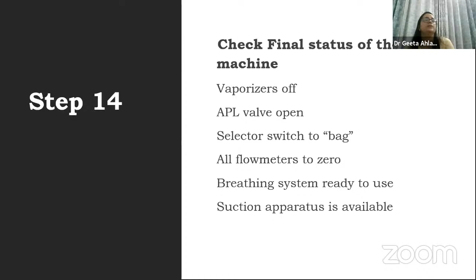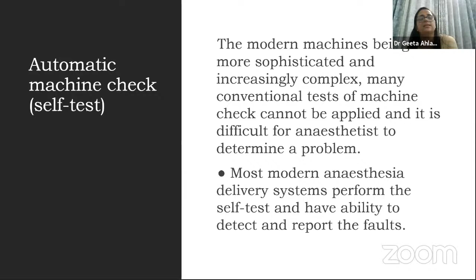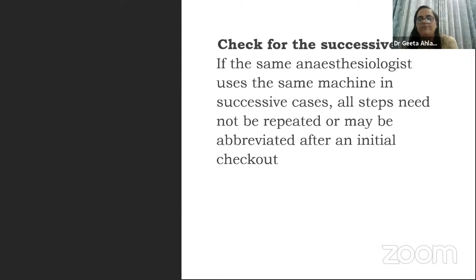These modern checklists, whatever we've mentioned, the conventional tests may not be possible in many of the modern machines which have automatic checks, self-tests. But for these machines, you should ensure that they are regularly serviced so that the self-tests are dependable. You should have at a glance: when was the machine serviced? Are the checklists and self-tests all okay? They are good, calibrated, then move ahead. If you're using the same machine for successive cases, you need not go through all the tedious tests, but a keen eye should be there in between changeover of all the cases.